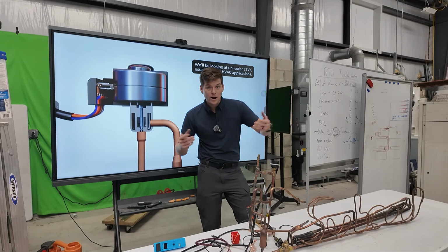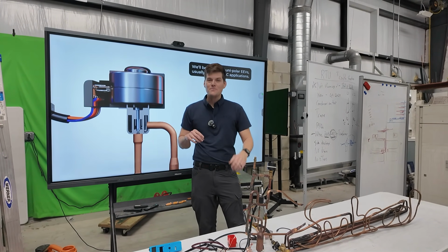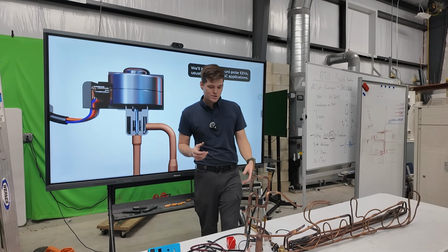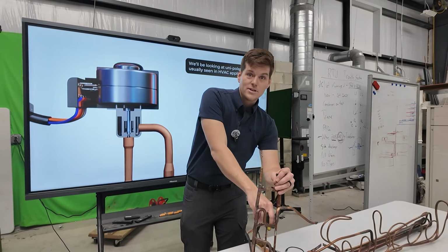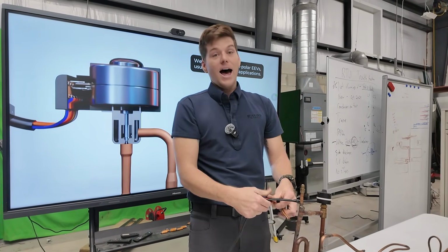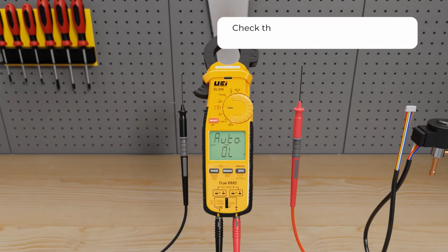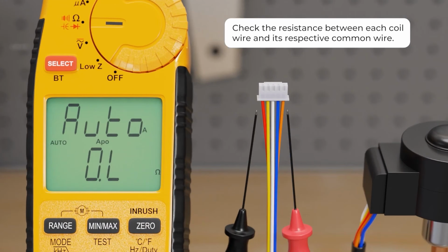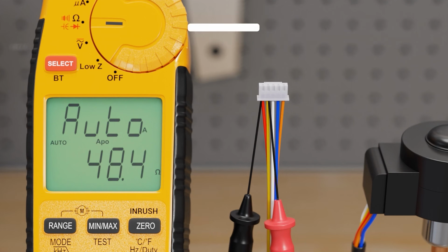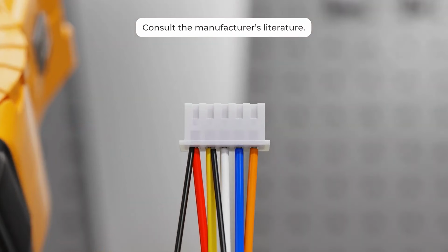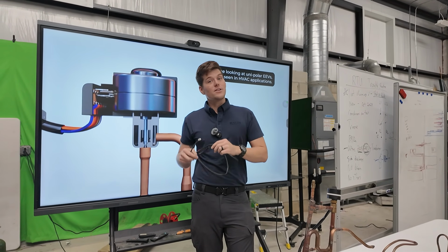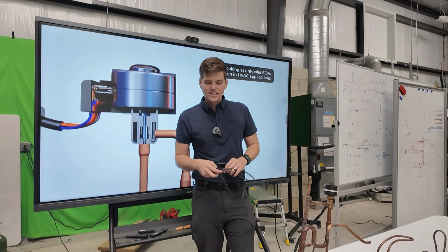Now that you've seen where they are, proved it to you, now we want to talk about how we troubleshoot them. With electronic expansion valves like this, we can check them electrically and see if they've actually failed with a multimeter, which we talk about in our 3D video. I always reference the service manual when looking at those electrical resistance readings to ensure that the valve you're testing is within the range that the manufacturer specifies is correct and accurate.